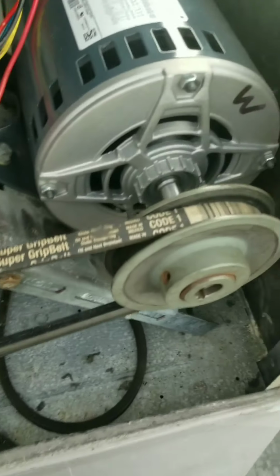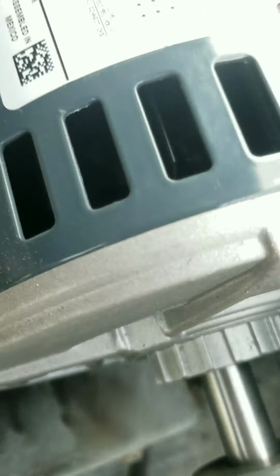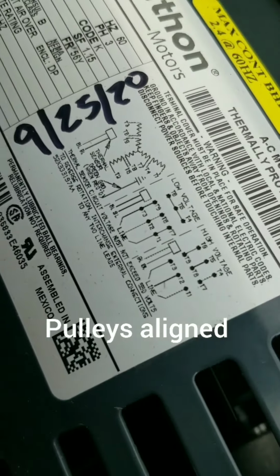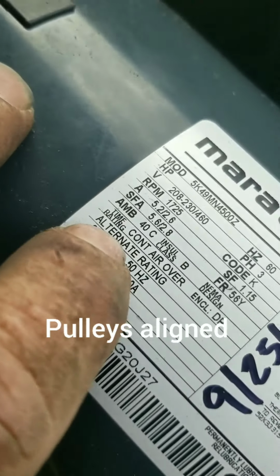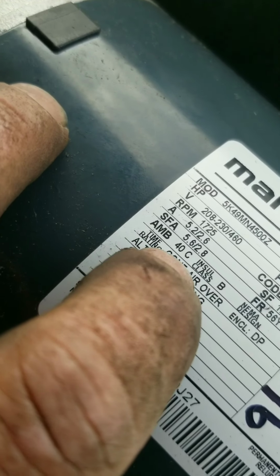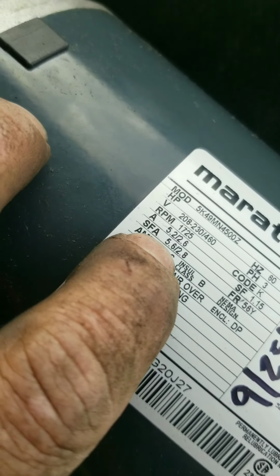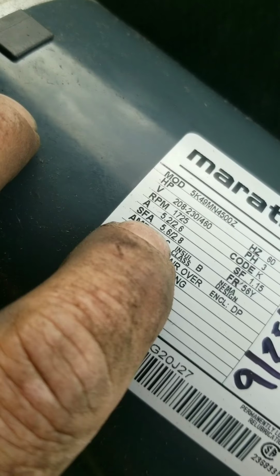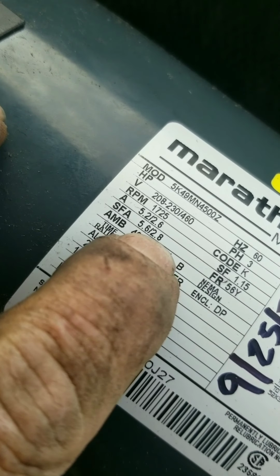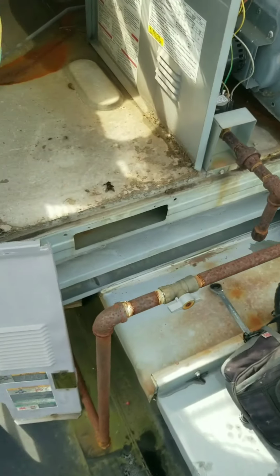So we got our new motor in. We verified all of our wiring. We got it dated, and we are allowed to run, let's see here. Service factor amps is going to be 2.8 at 460 volts. So we're going to keep this guy on and verify our operation and our amp draw.